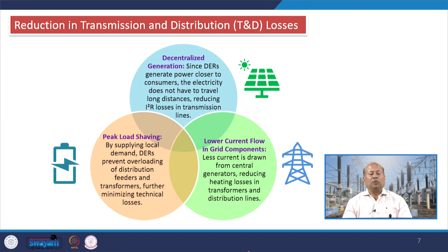So, your transformer loading will be significantly reduced once you are locally generating and engaging them to cater to the local loads. And the lower current flow, as I told you, the grid component will experience lower current flow because you are feeding a few amperes of current from the local consumers through DER integrations.